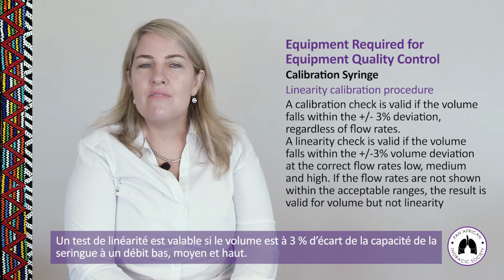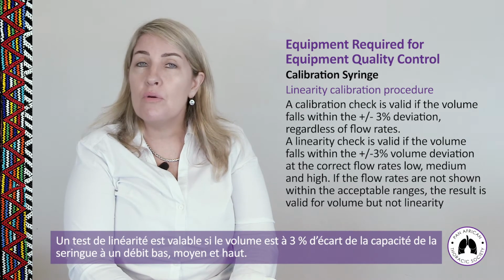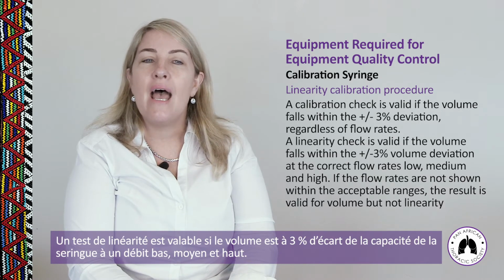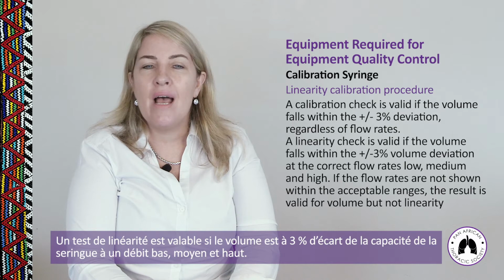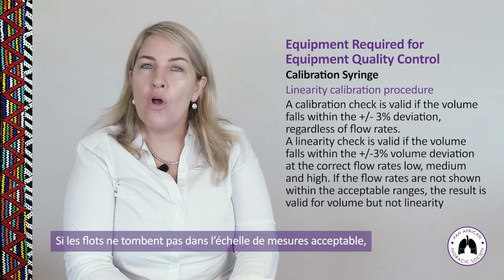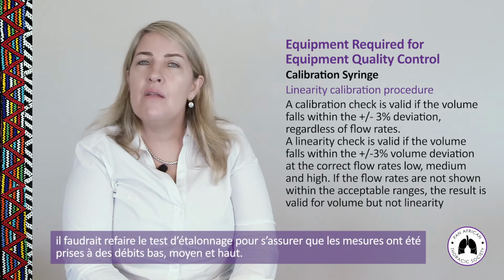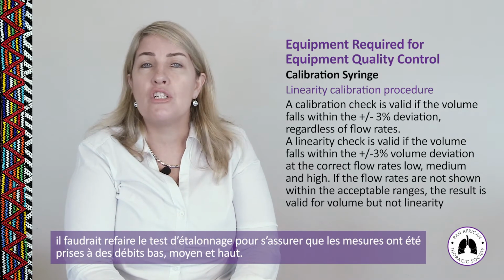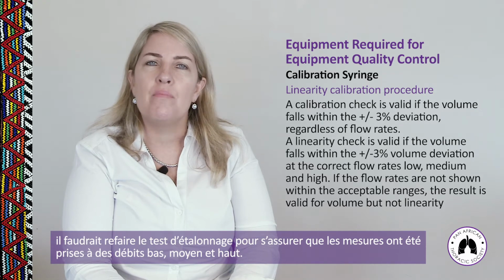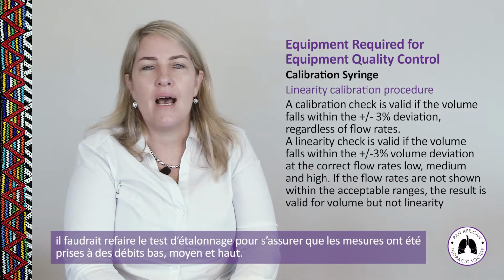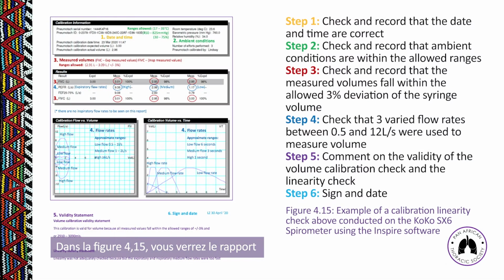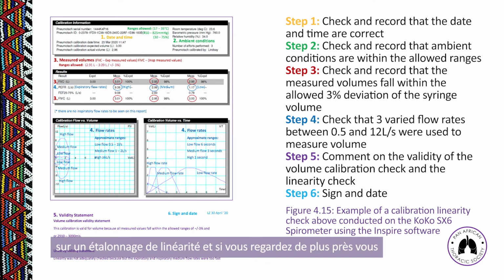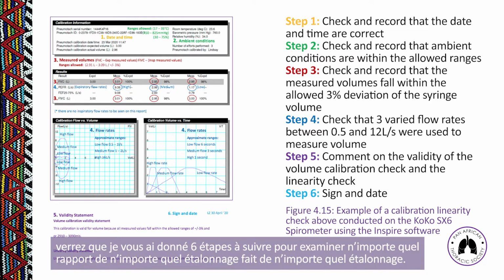A linearity check is valid if the volume falls within plus or minus 3% volume deviation at low flow, medium flow, and high flow. If the flow rates are not within acceptable ranges, then we would want to try and redo the calibration check again to be sure that we've checked volume across the flow ranges, low, medium, and high. In figure 4.15, you'll see a linearity calibration report. And if you look very carefully, you will see that I've shown you 6 very clear steps to looking at the report of any calibration done on any spirometer.